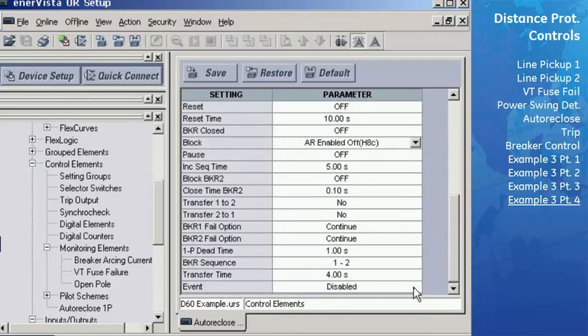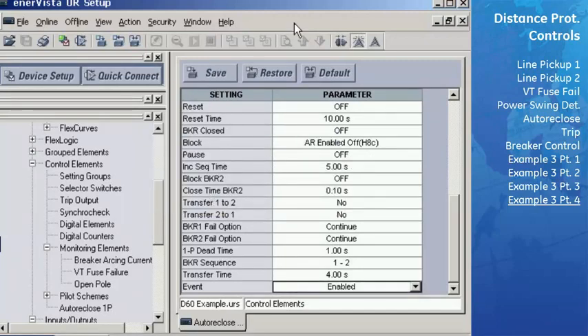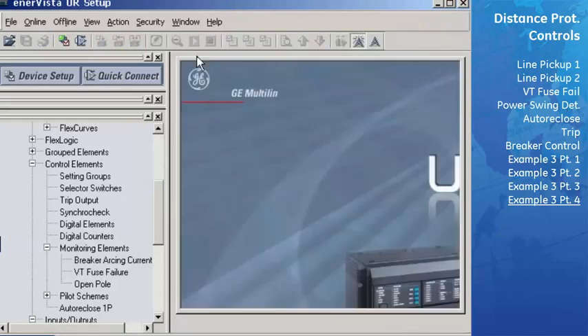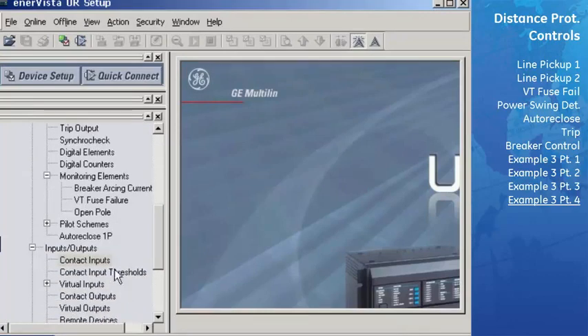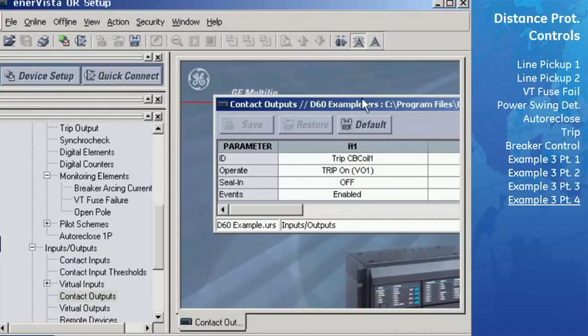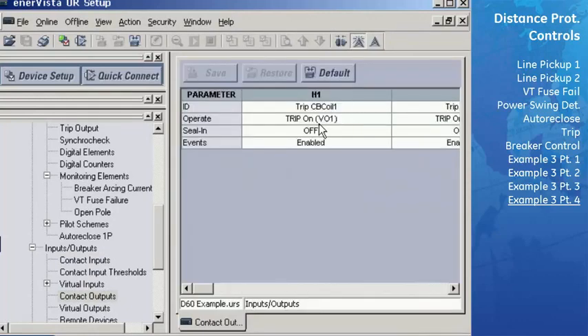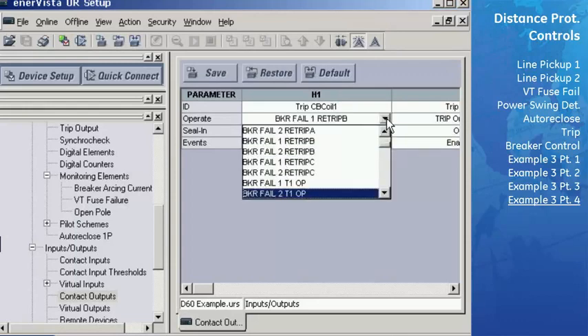The only other setting needed is to set Event to Enabled. Then save these settings to the Settings file and close this window. The last settings that need to be configured are to assign the proper signals to the output contacts for tripping. Go to Inputs Outputs, Contact Outputs menu. Change the operate signals for both H1 and H2 to breaker 1 off command. This is the tripping signal from the breaker control logic.